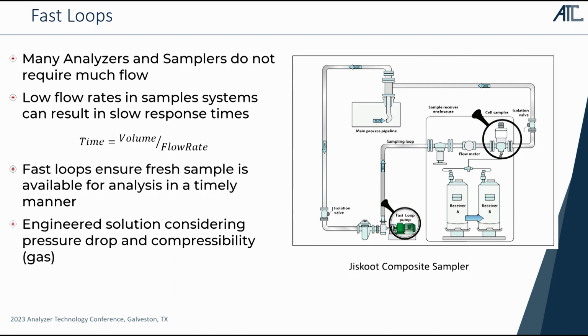So, like we said, many analyzers, many samplers don't require a lot of flow for them to operate, but we need flow in the fast loop in order to get a good response time. If you've been through the Tony Waters training or came to my class this week, we talk about how the time delay in a system is the volume divided by the flow rate. So if we want to get fast response, we either have to keep our sample system volumes low, or we have to have a lot of flow.